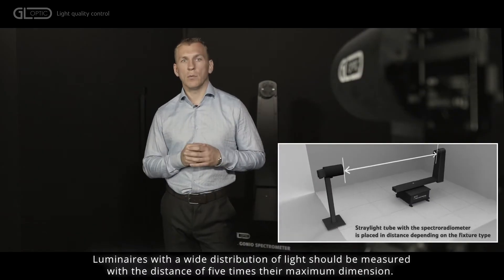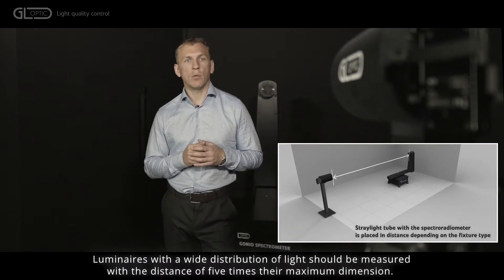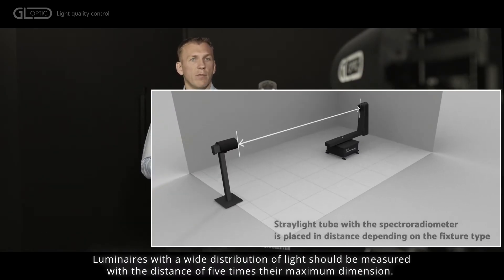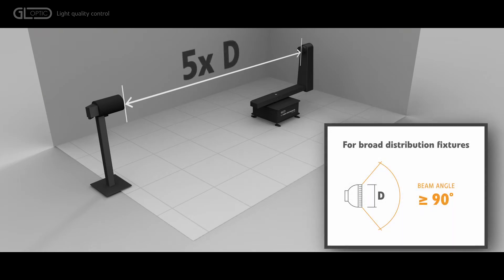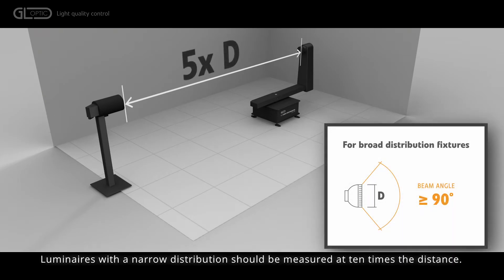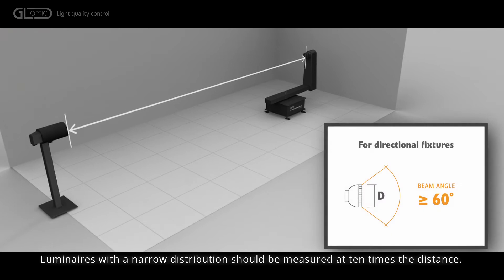Luminaires with wide distribution of light should be measured with the distance of five times their maximum dimension. Luminaires with narrow distribution should be measured at ten times the distance.